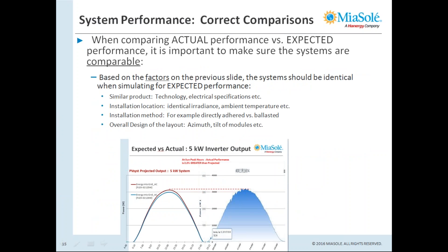When a customer says they're disappointed in system performance, we must understand what the expectations are and whether they were technically sound. We need to compare actual performance to expected performance modeled with the exact same system assumptions — the same tilt, azimuth, same product, same location. These factors are all critical to coming up with correct and comparable expectations.